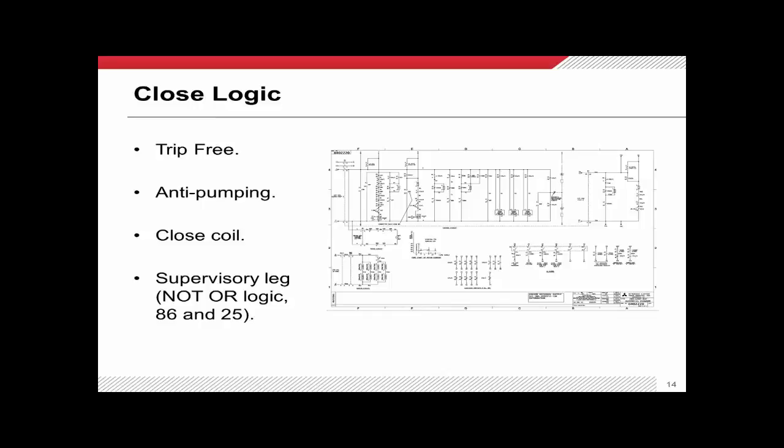This is a trip free circuit breaker, and there is an anti-pumping scheme right over here. To 'pump' a circuit breaker means you put a standing trip and a standing close on it simultaneously — trip, close, trip, close, trip, close. After about two or three cycles you'll have to stop and recharge the spring, then it starts right back up. Eventually something in the circuit breaker will fail — most likely you'll burn up either the trip coil or the close coil.